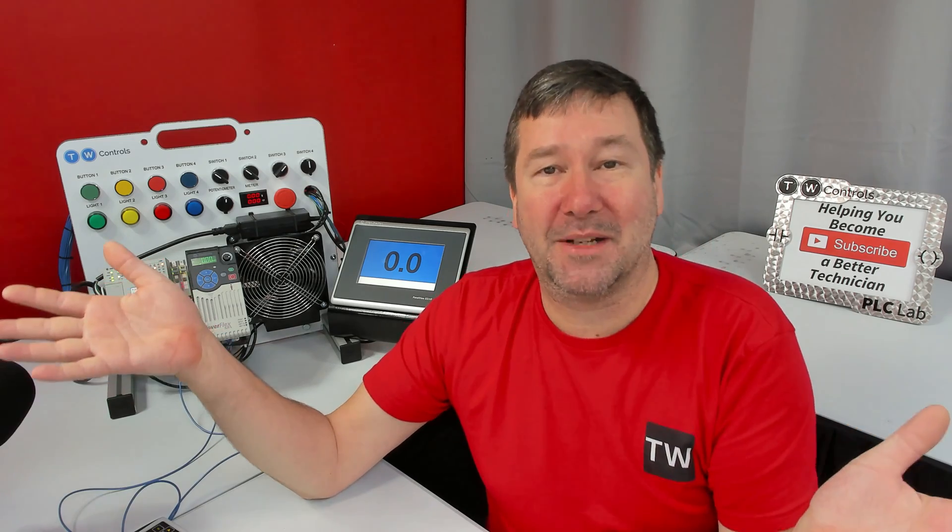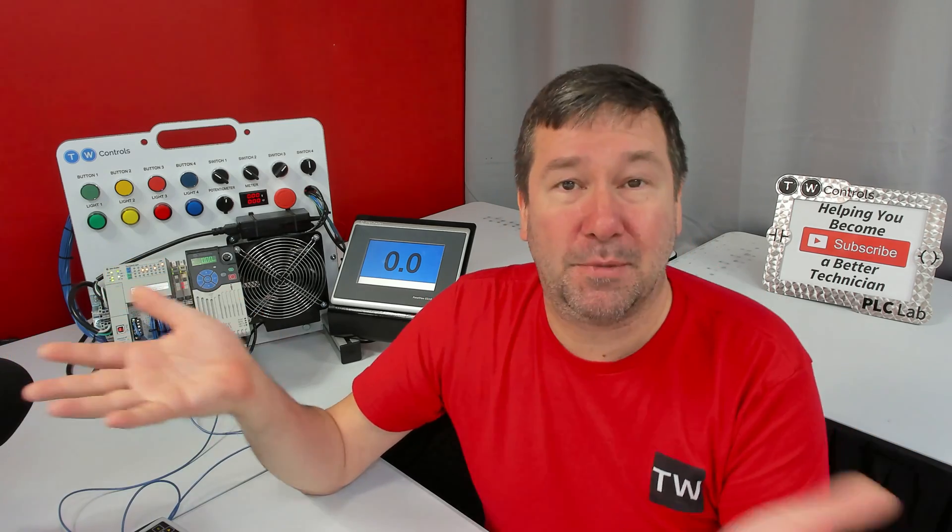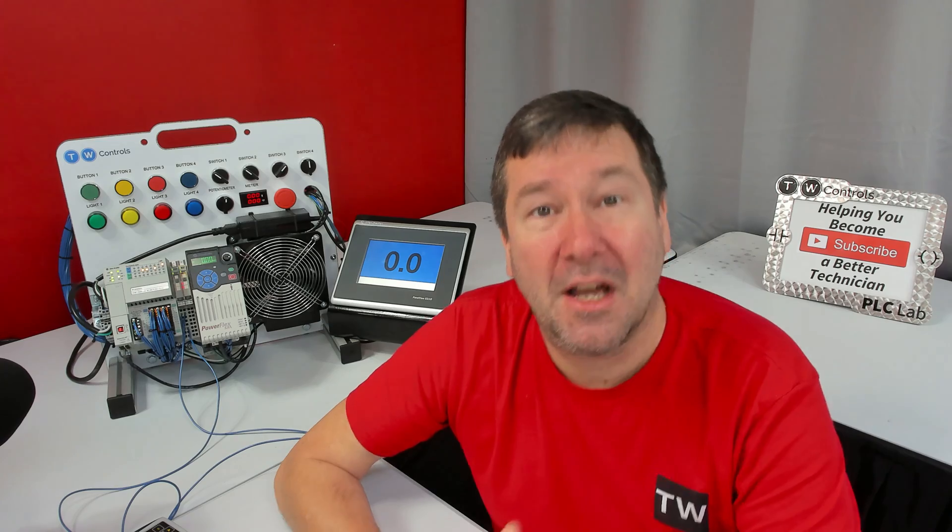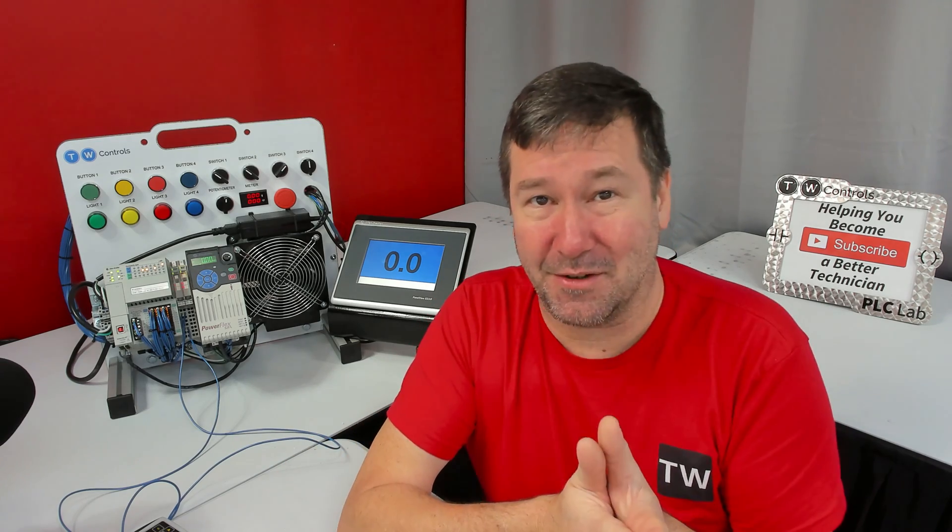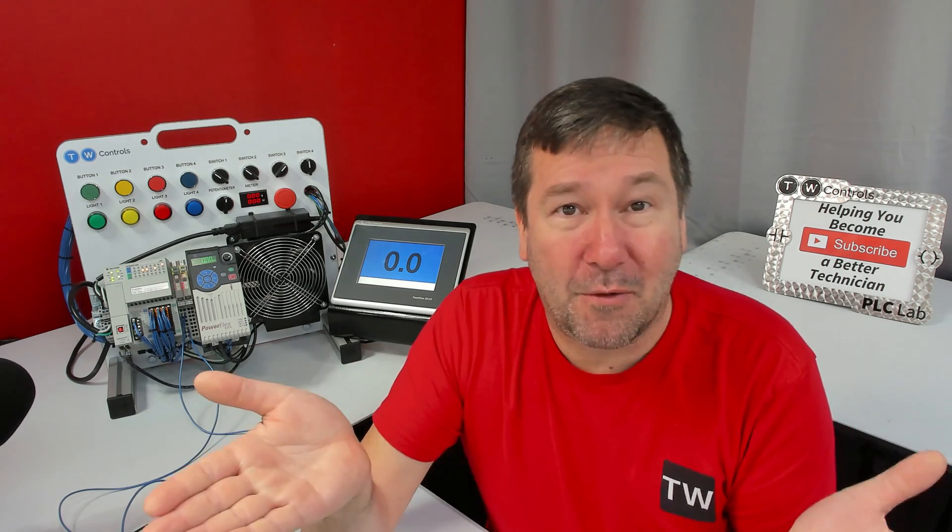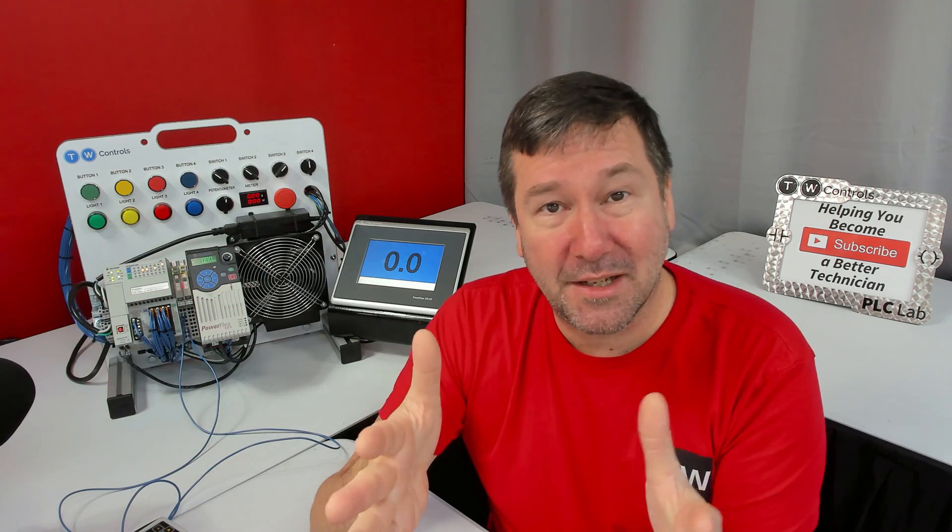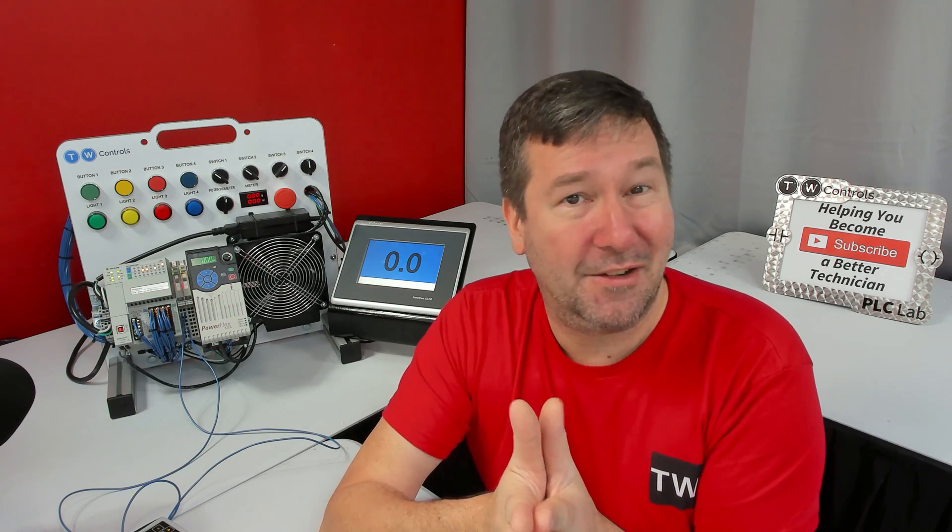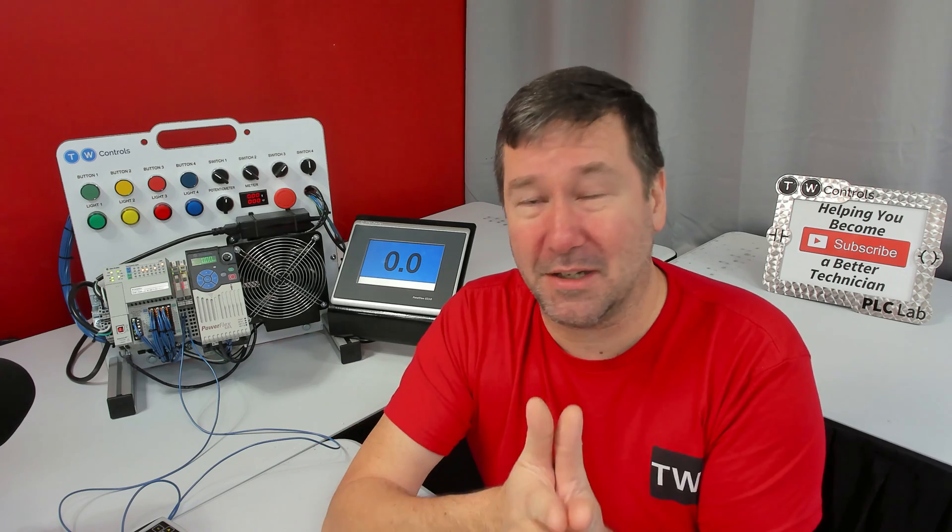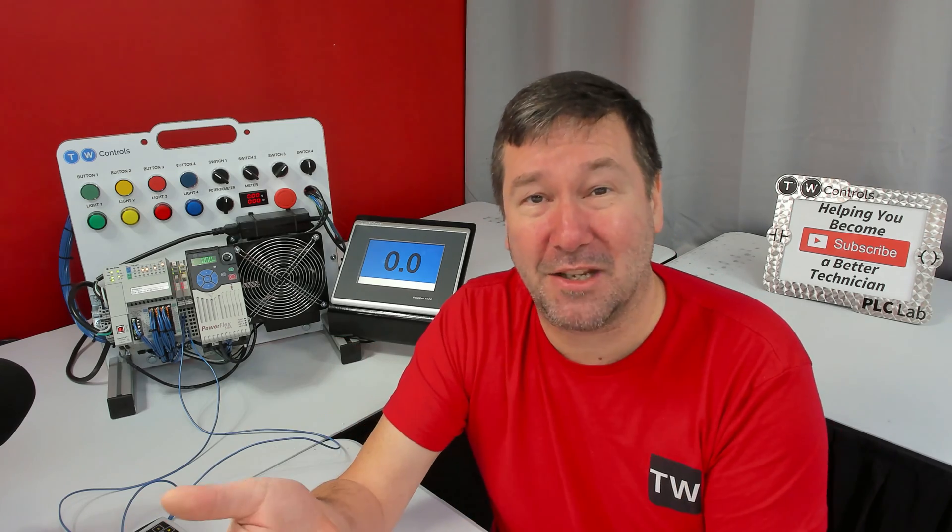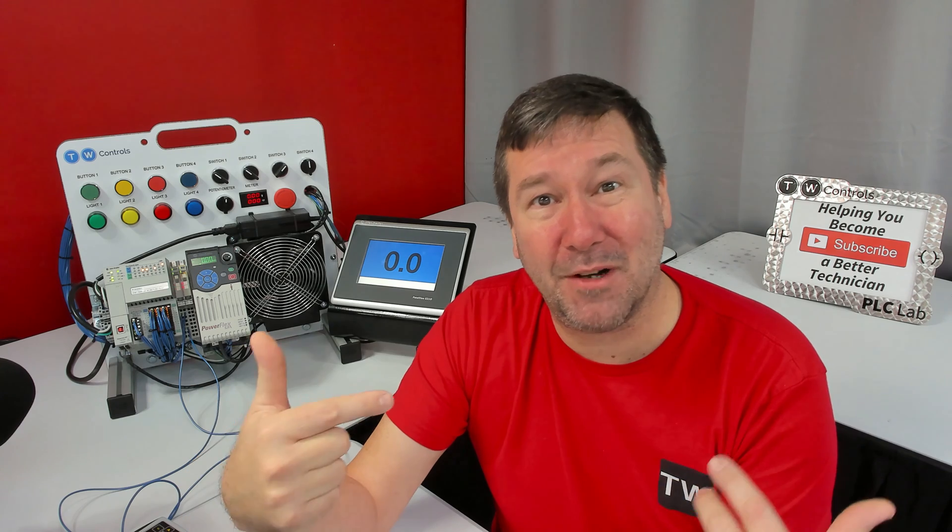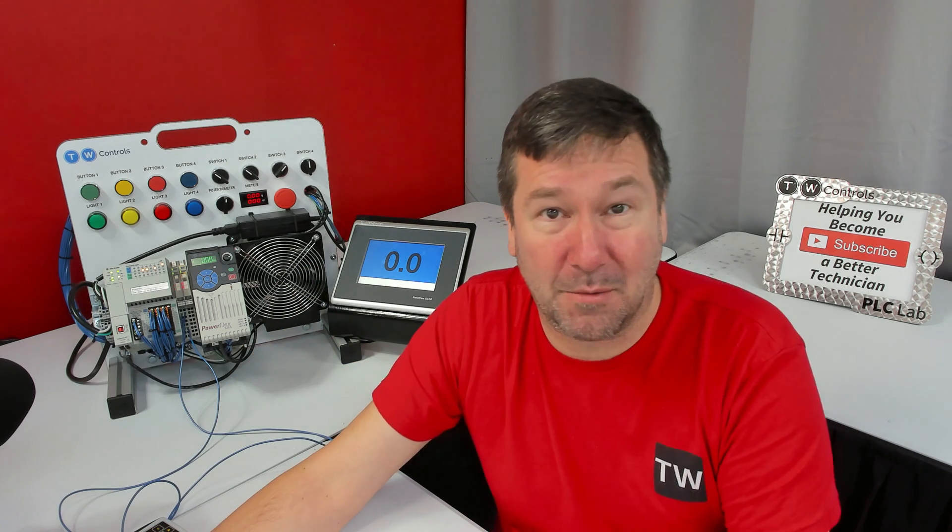Now, someone is going to tell me in the comments, well, all you had to do was put the values you want in those. But the issue is that's scaling in the integer. So those are whole numbers. I want four to 20 milliamps. So I'm losing resolution as I bring those down. So you really don't want to do that. You want to keep those. I personally feel at their default units, because that's what I'm going to be familiar with when I go to troubleshoot.